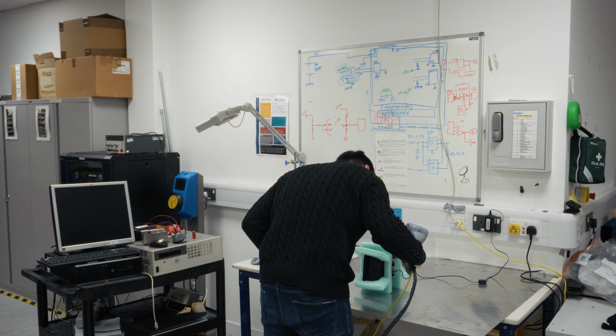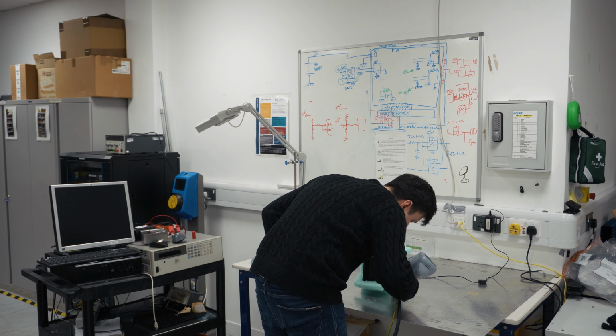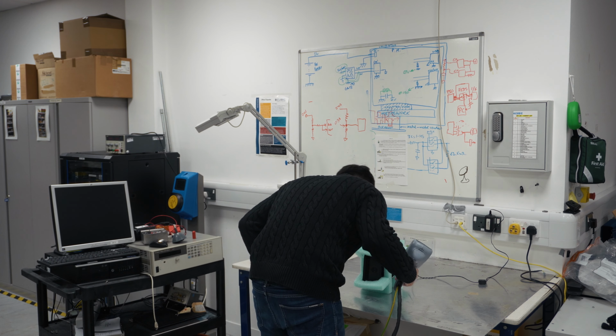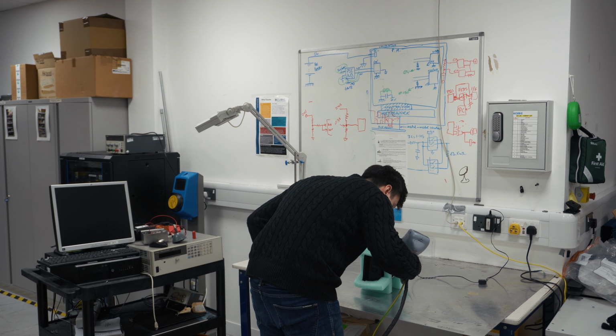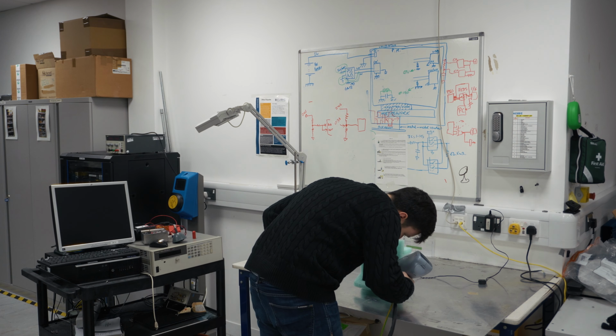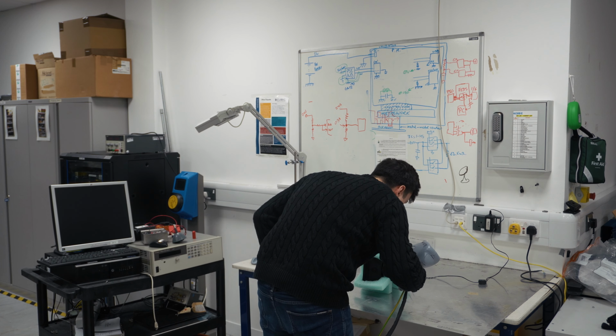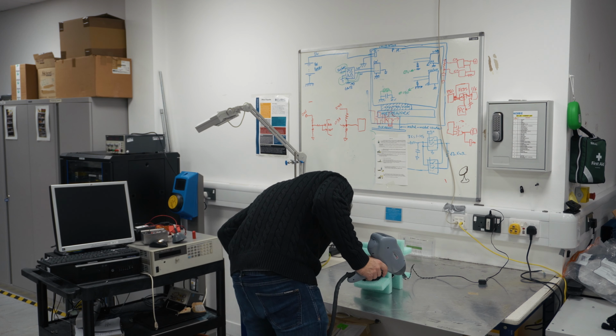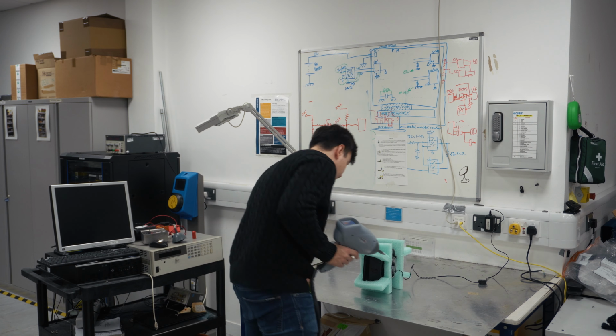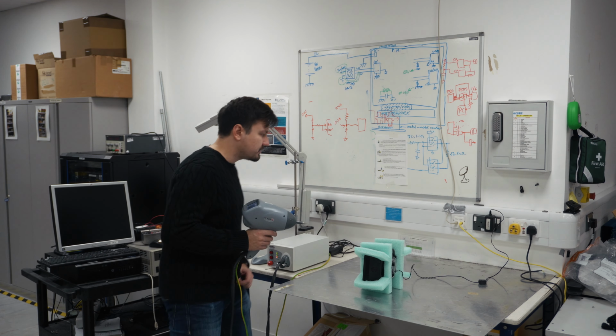Now I'm going to go to positive polarity and repeat the test at 8 kilovolt contact discharge level. That was a big one. Okay, nothing's happening still. Oh, the device actually turned off.